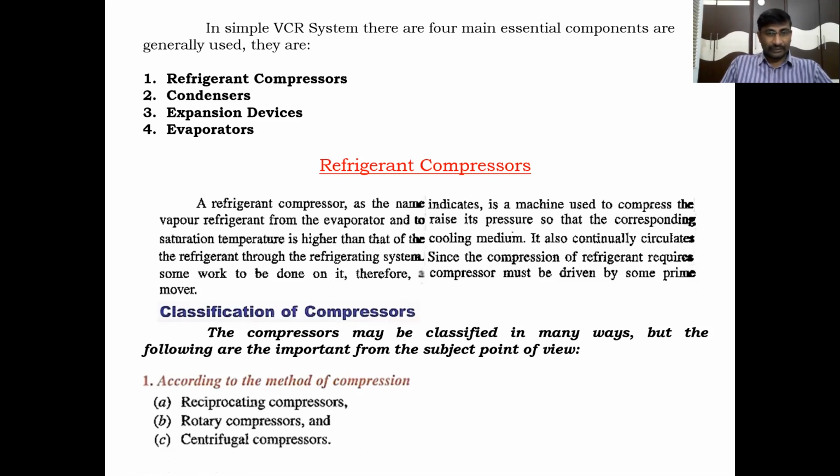Backflow does not occur in these two compressors because they have valves which do not allow the compressed refrigerant to flow back into the compressor. But in centrifugal compressors at part loads, backflow occurs from the high pressure side to the low pressure side, and the refrigerant flows again into the compressor when the centrifugal compressor is in shut-off condition. That's why it is not positive displacement. These two are positive displacement.